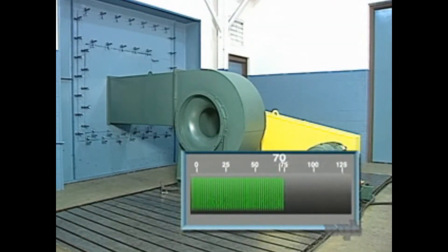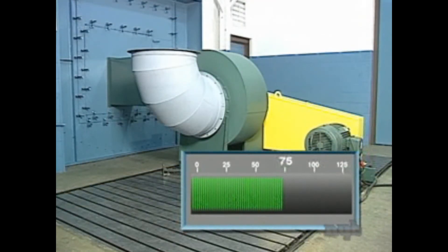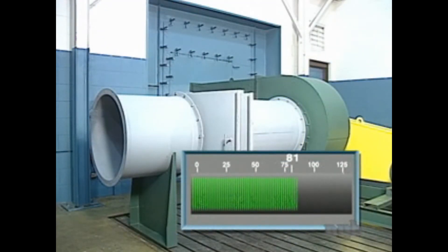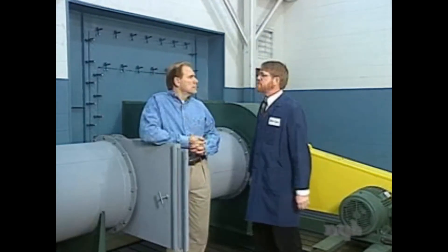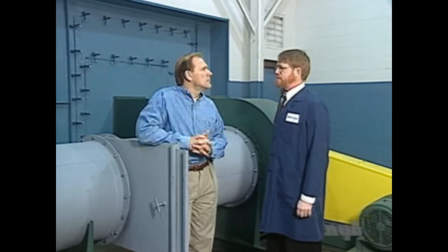Here's a fan operating with an open inlet. Air enters the fan smoothly and the fan wheel is loaded uniformly. Now we've modified the inlet condition with an abrupt 90-degree inlet — you can hear the difference. The abrupt inlet is causing the air to separate and become turbulent as it enters the fan. In this example, we've modified the fan with another poor inlet condition: a typical blast gate. Again, you can hear the difference. These are just two examples of increased sound levels created by system effects.